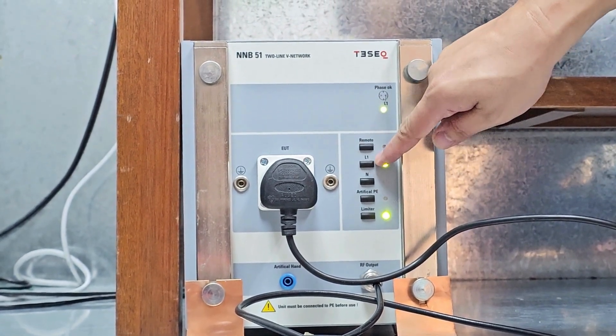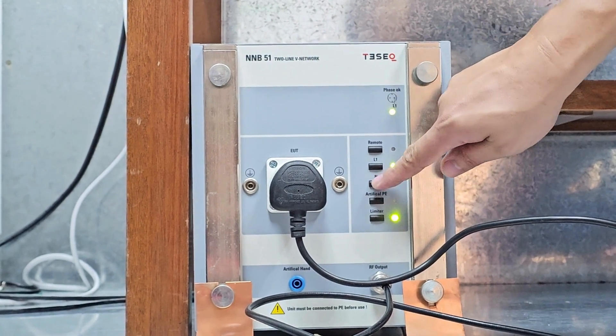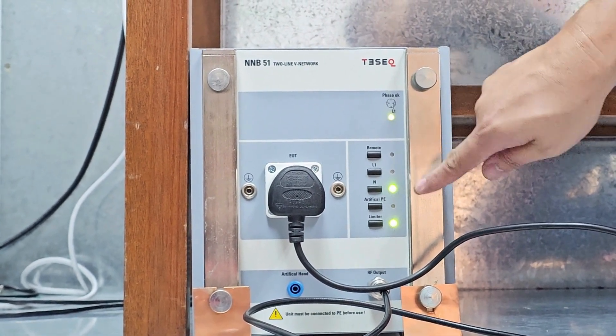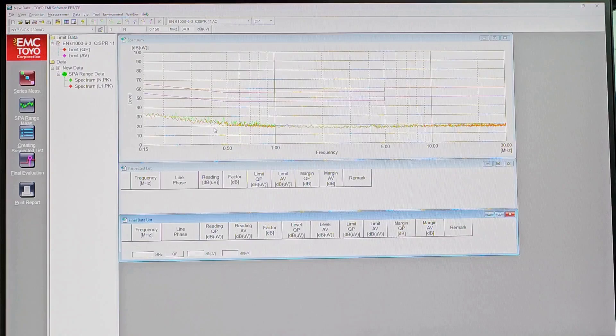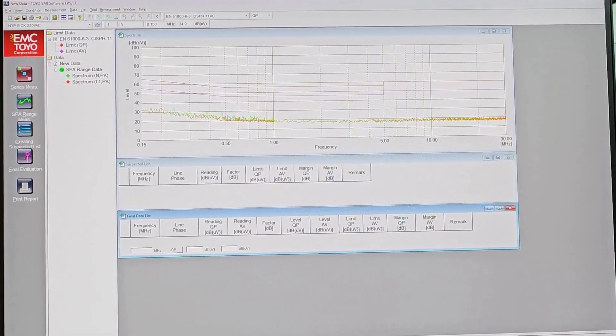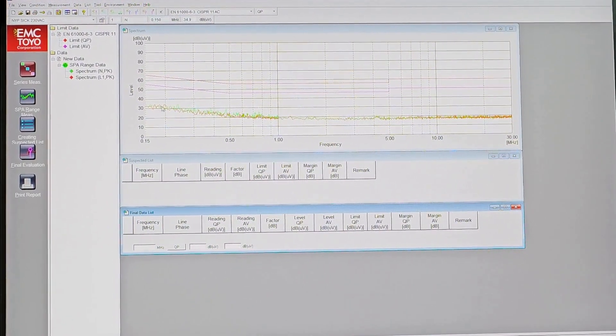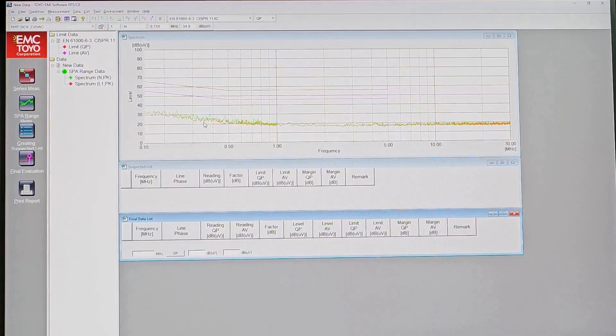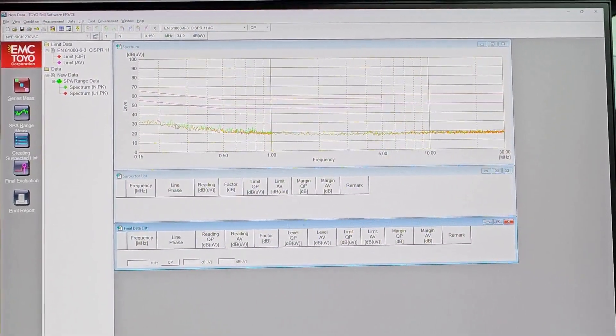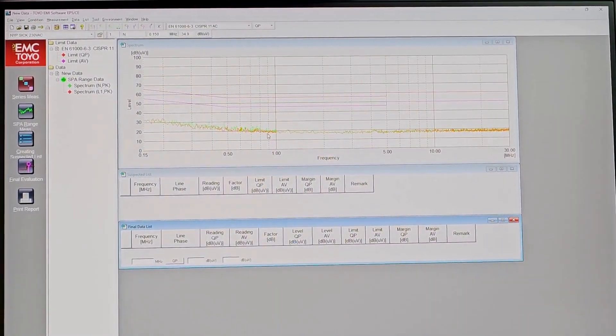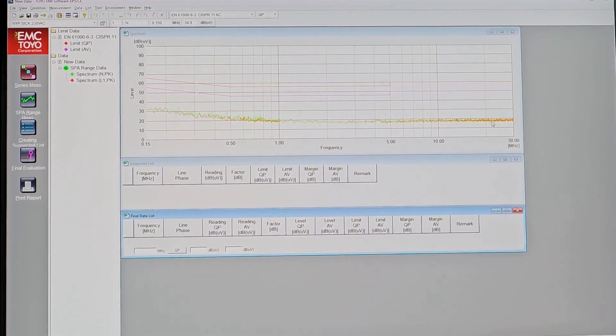I need to toggle between line and neutral as shown earlier. The system requests us to set to neutral, so I press neutral to ensure the indicator appears at neutral. Initially, we always perform a noise floor measurement with the LISN not connected to any DUT. You can see two colors — green for neutral and red for line — which indicates the noise floor of the LISN without any DUT connected, ensuring good measurement quality.